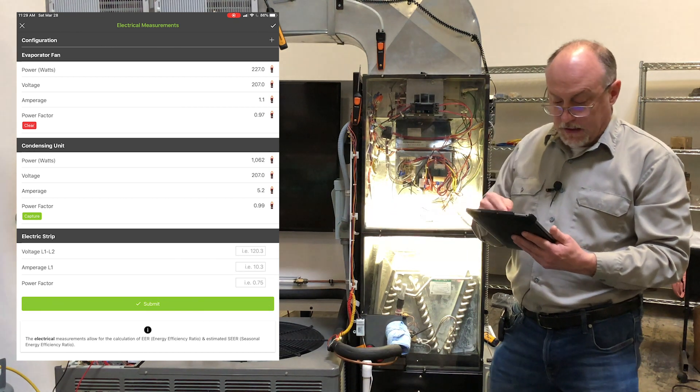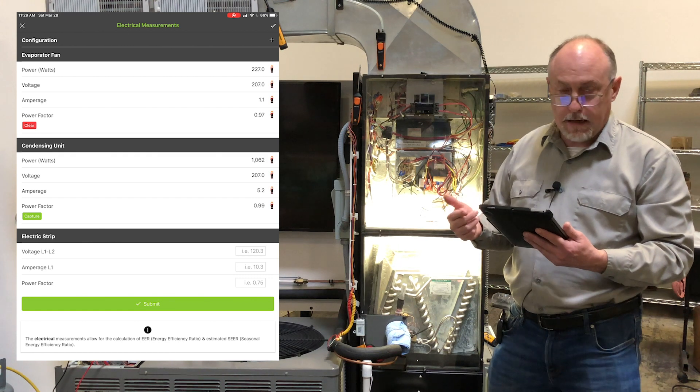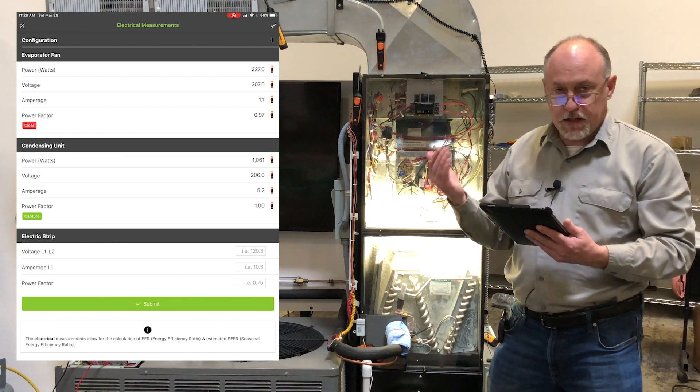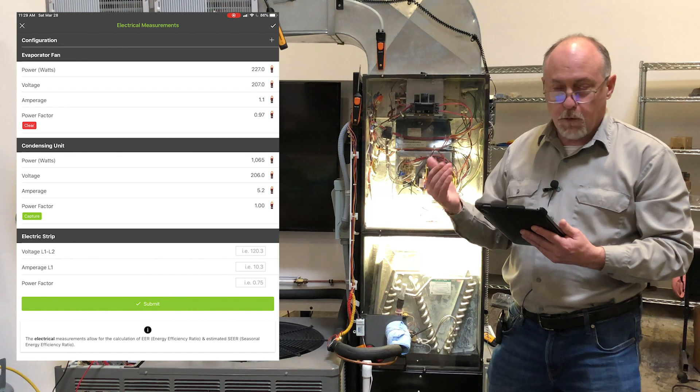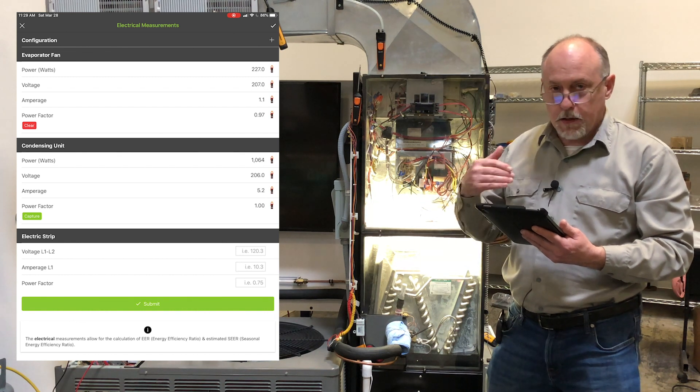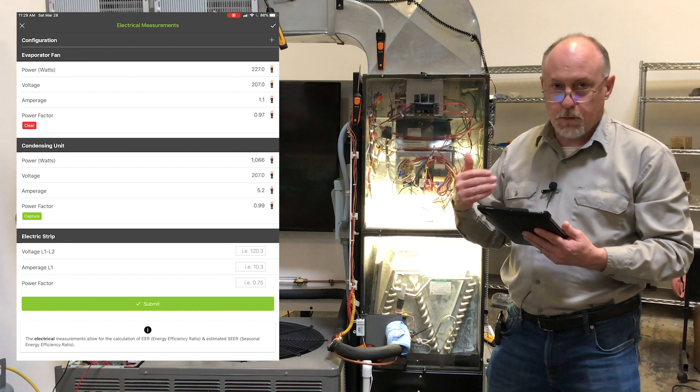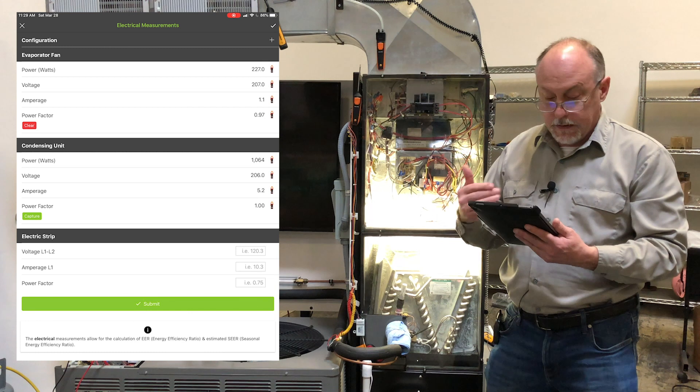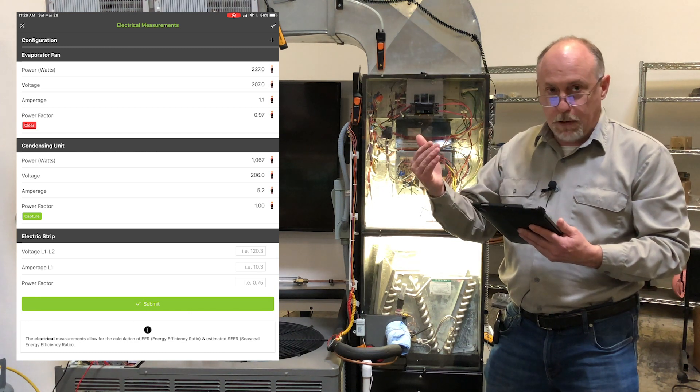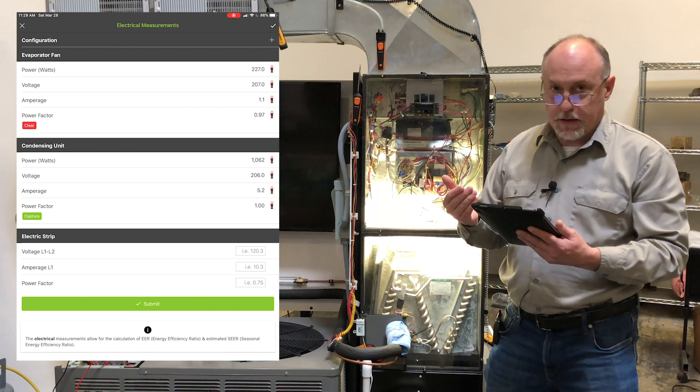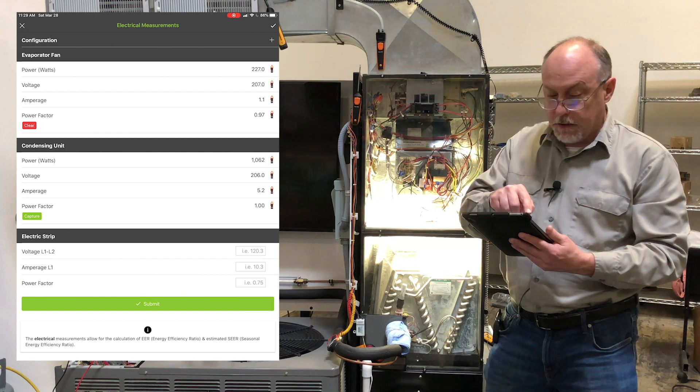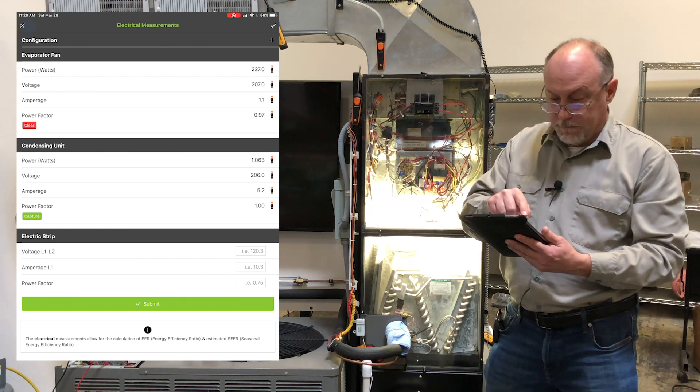You want to wait a few minutes for the system to stabilize. And that's what I have the condensing units actually streaming in live. So I want to wait till the condensing unit reaches its stability before I capture the electrical data. Because as the system runs, the condensing unit watts will creep up. And so we want to capture it and get an accurate representation of the SEER while we're doing that.